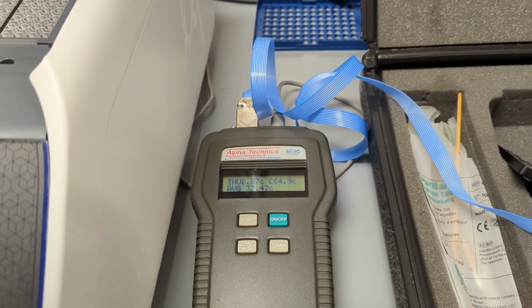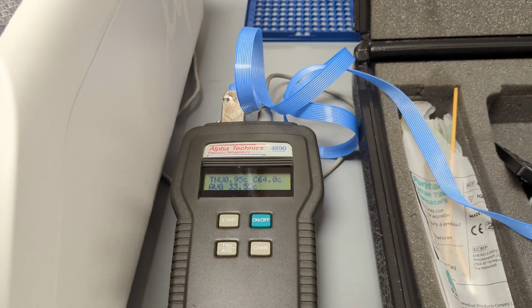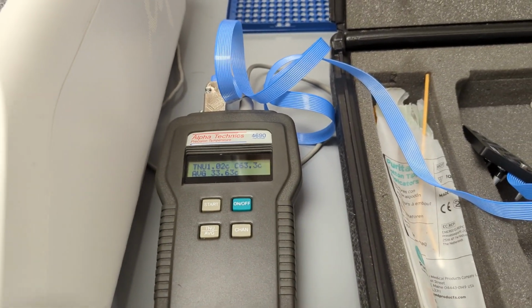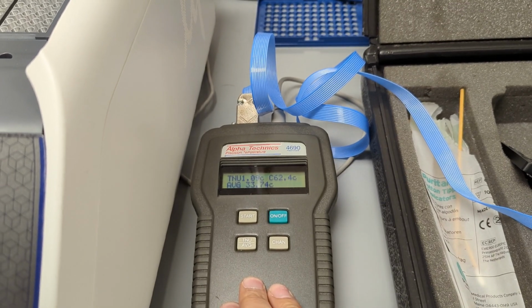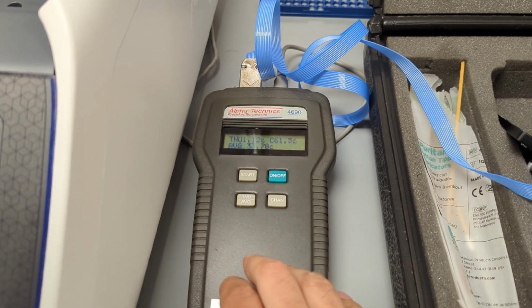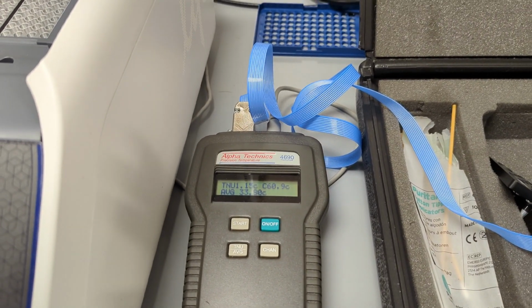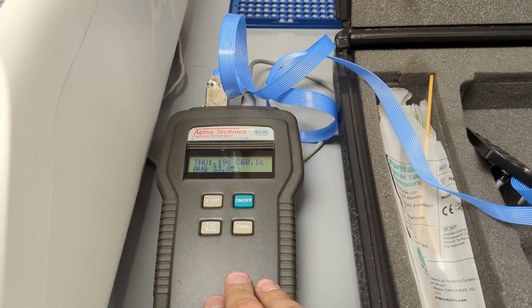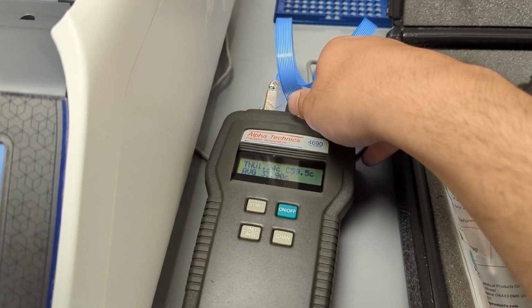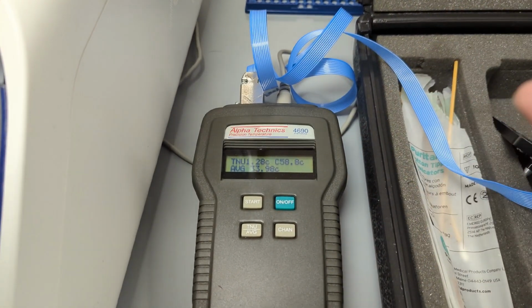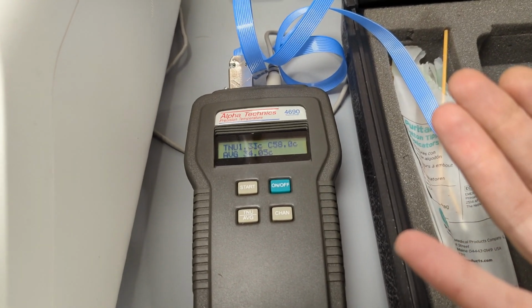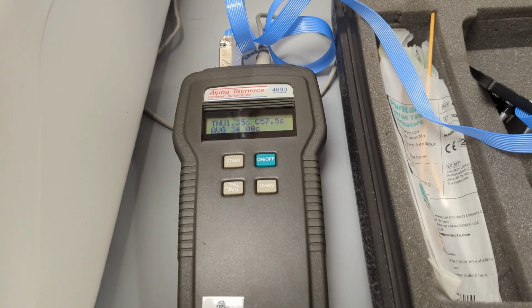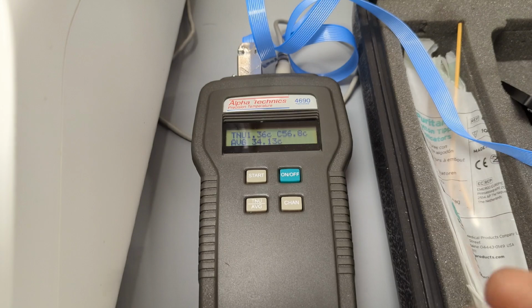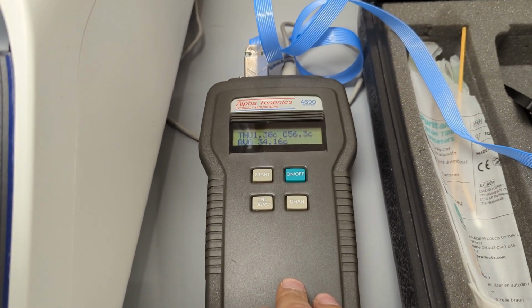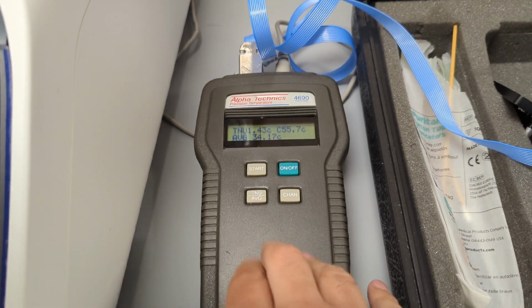I use another third-party calibration service for some of my other calibration standards, like tachometers and other digital thermometers, and they do great work. They advertise that they can calibrate this, and that depends on what your definition of calibration is. If you're just verifying it with another standard, yeah, they can do that. But if it's out of tolerance, they can't make the adjustment. They don't know how, they don't have the procedure, which is why, if you're advertising as a calibration service company, I would assume that you can do the calibration adjustment for whatever you're advertising. Or you should at least state that. It shouldn't be on you, and that's kind of what they told me. So anyway, I would not use anyone for these but the manufacturer, just to save you some money.